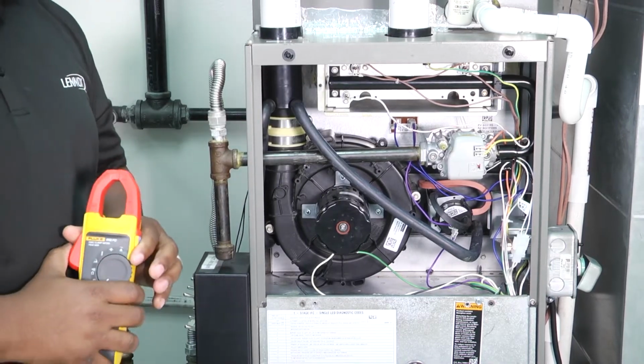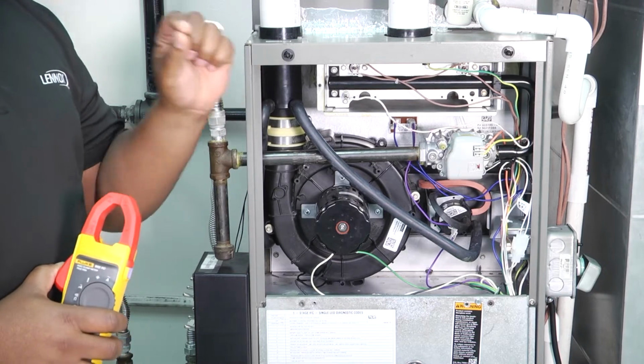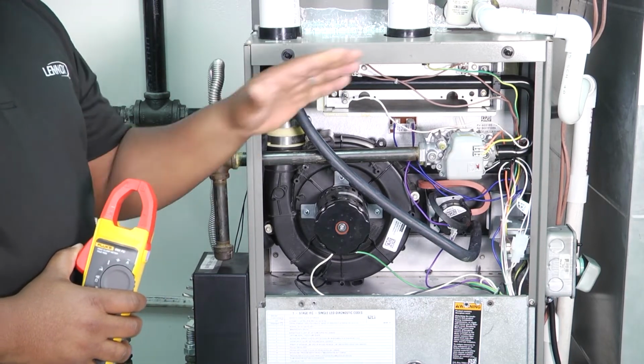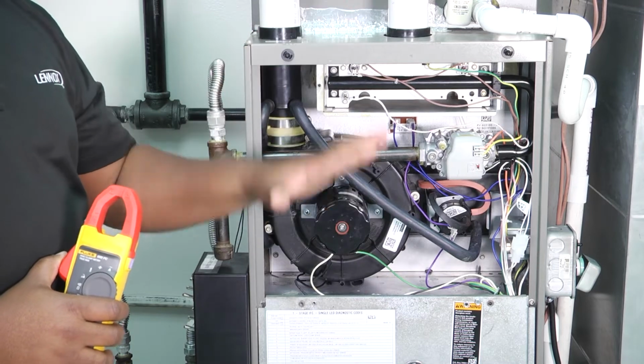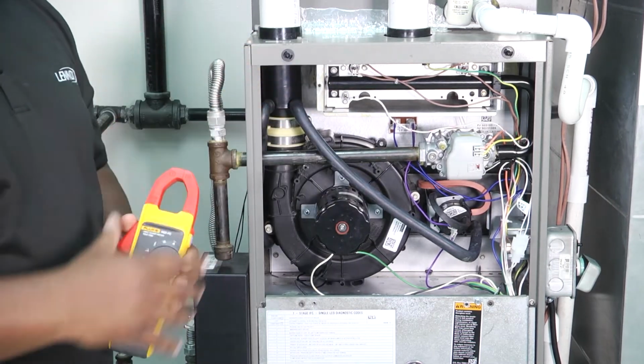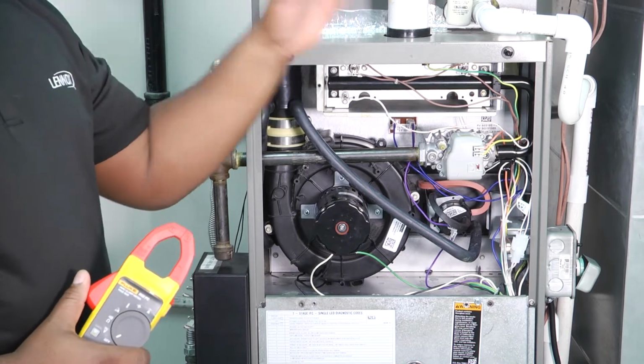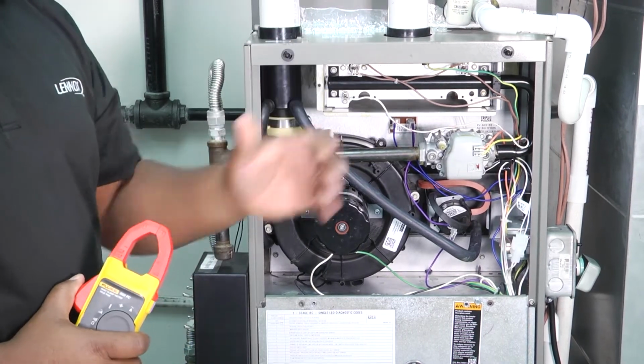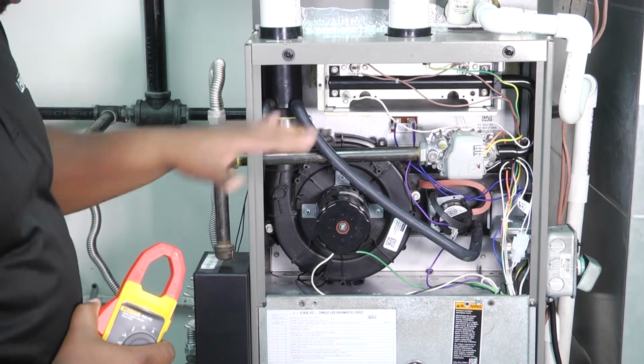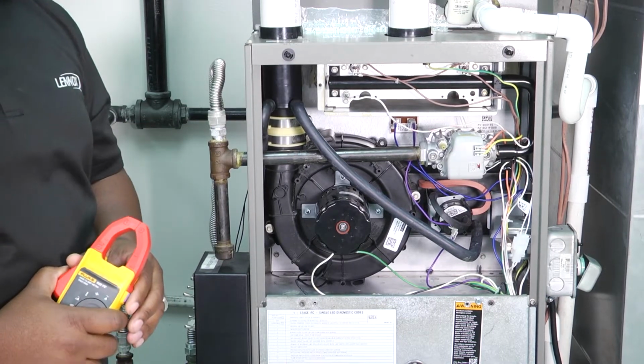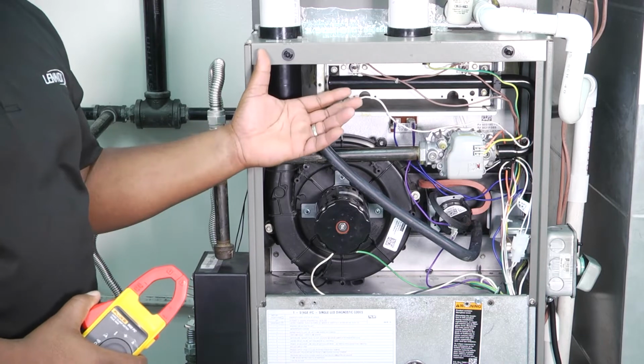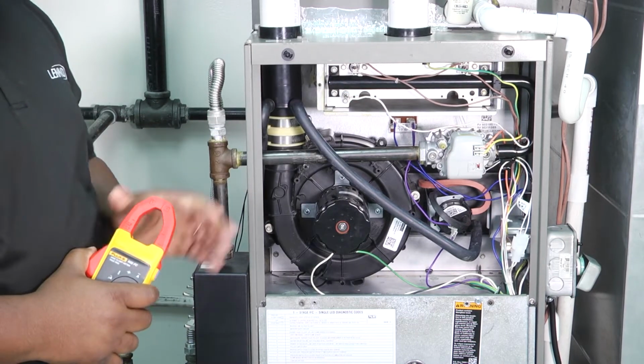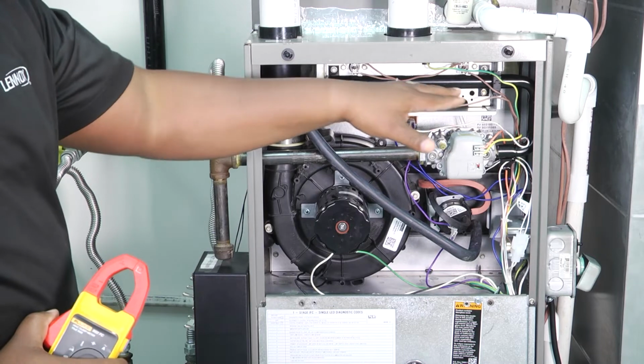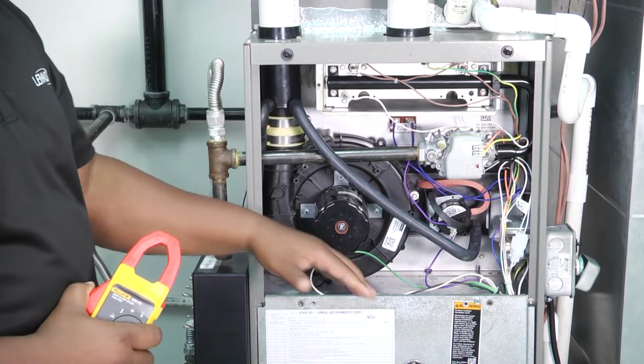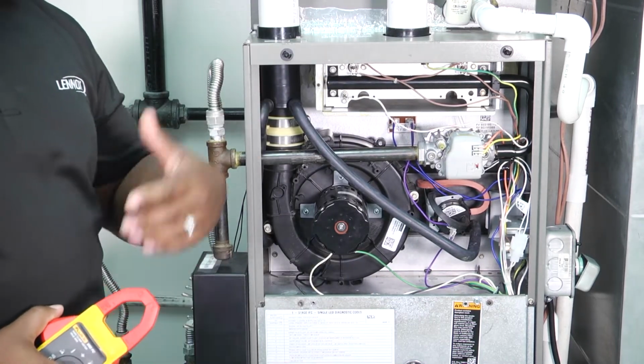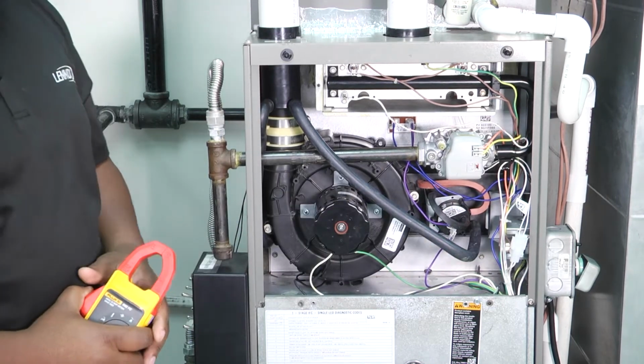One note is that when you test the igniter, it is best to test that very early on. Once that igniter has heated up and fired a couple of times, those resistances could change. So you want to check that right away and get it at its earliest and coldest stage if you can. Now, the other particular component that you want to check in conjunction with that is our good friend, the flame sensor, right? Our flame sensor's job is to prove that we have a flame and send a message to the board saying that it's okay to initiate the next stage in the sequence of operation.